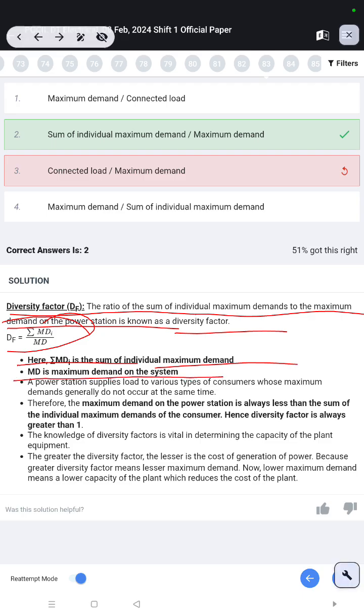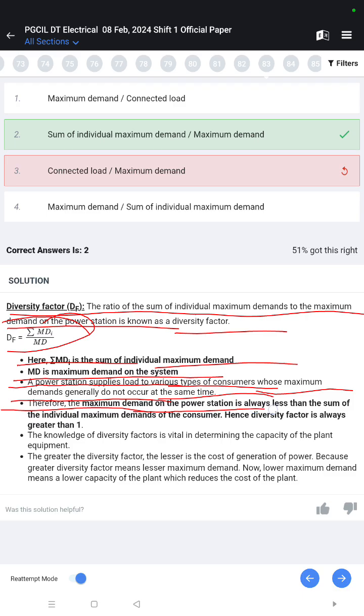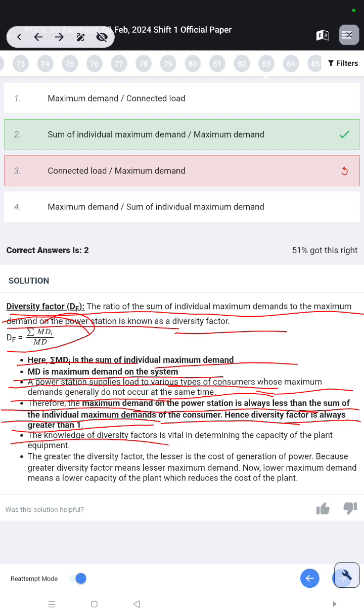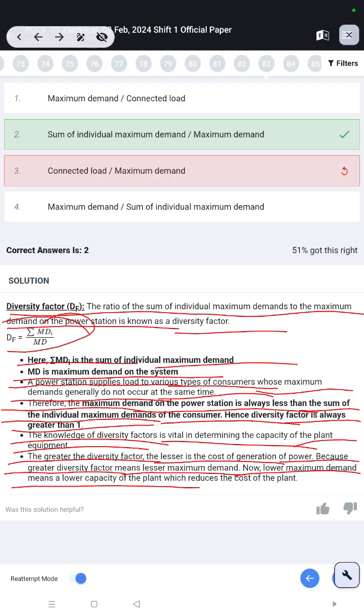A power station supplies load to various types of consumers whose maximum demands generally do not occur at the same time. Therefore, the maximum demand on the power station is always less than the sum of individual maximum demands of the consumers. Hence, diversity factor is always greater than 1. The knowledge of diversity factor is vital in determining the capacity of the plant equipment. The greater the diversity factor, the lesser is the cost of generation of power, because greater diversity factor means lesser maximum demand. Now, lower maximum demand means a lower capacity of the plant, which reduces the cost of the plant.